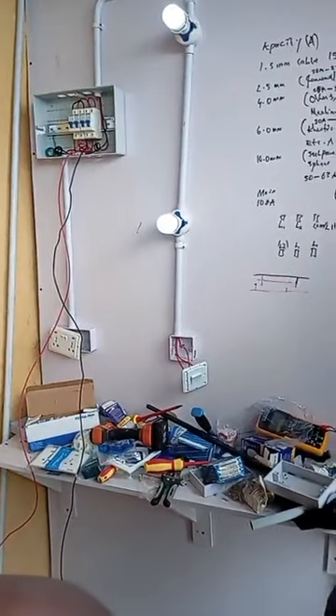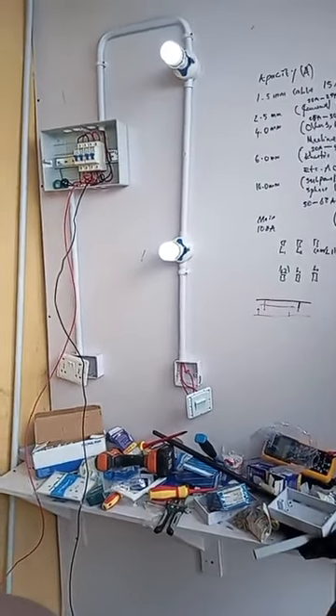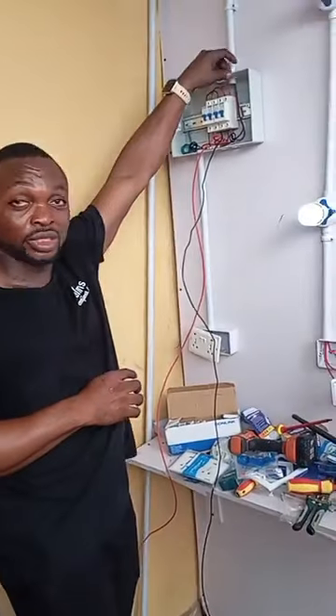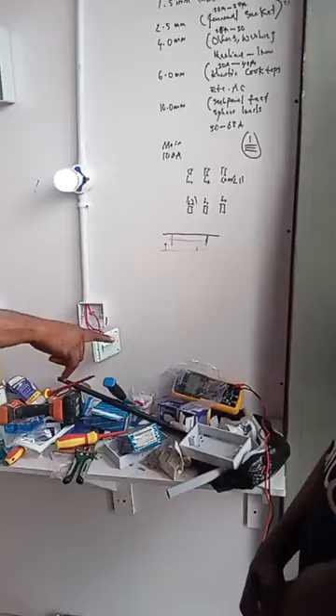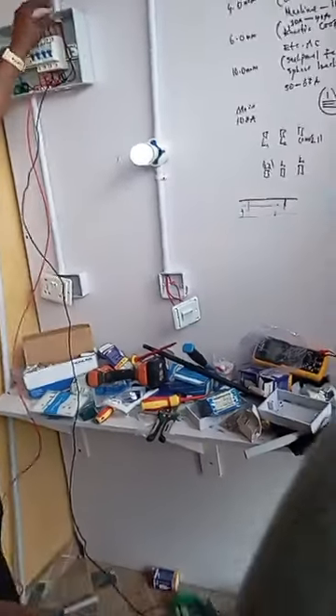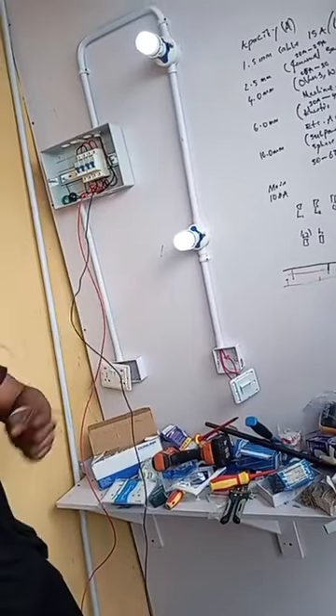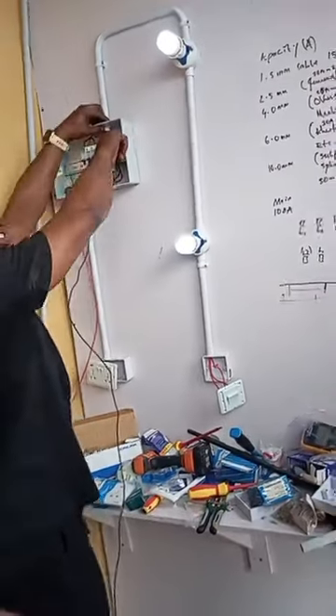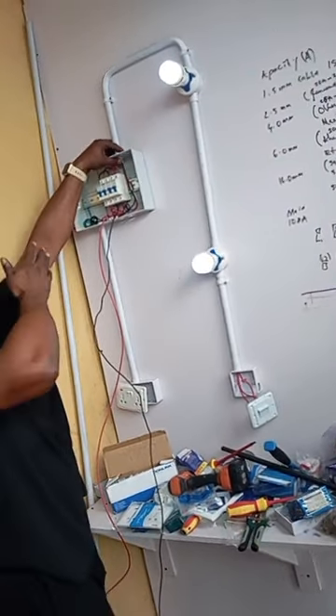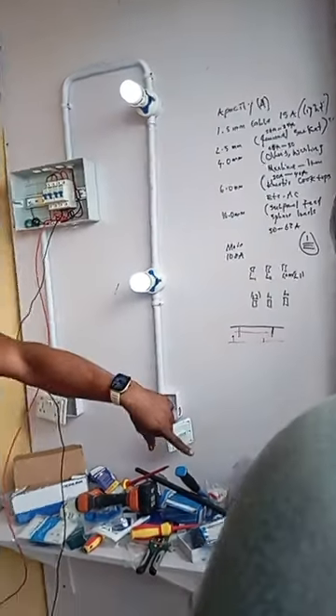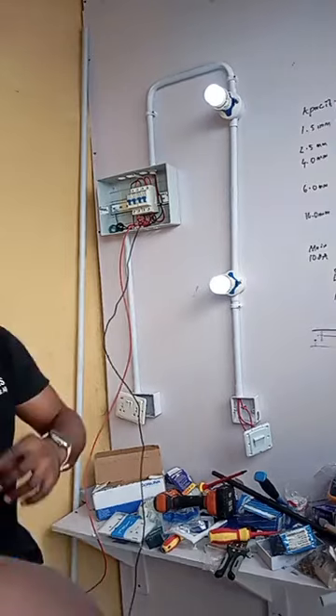Sorry, there's no need to put any cushion if you want to do it properly on the box. No, we use it if it's the distribution board, the iron one. The mount here is for 20mm - the size is already there, it's 20mm. They have 25mm, and like that one now, you still find this 25mm, you still find 20mm. So you can still use within 20. If not, why do we normally put it here? So that when you are drawing your cable, during fixing of cable, the insulators will not tear. Because if I start dragging this cable by force here now, the insulators will tear, which will lead to leakage. So it's very important to put it properly.